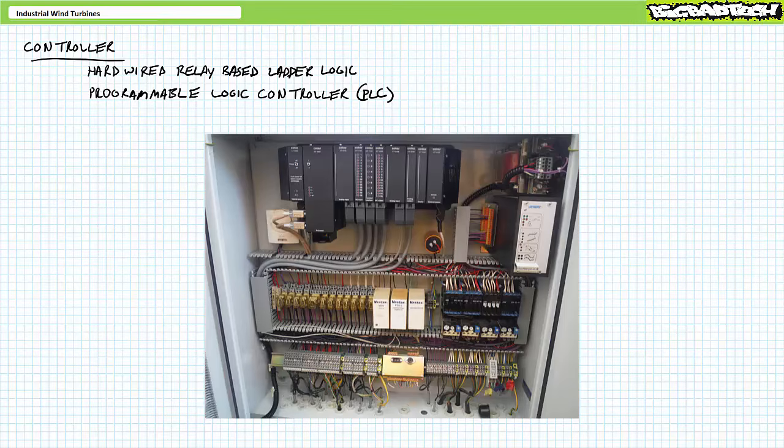Depending upon construction, the controller takes inputs from various sensors and switches, evaluates these inputs, and issues outputs to actuators like motors and brakes. The evaluation of inputs might be real electromechanical contacts wired together, or they may be programmed instructions inside a PLC. Depending upon the model and date of manufacture, interacting with the controller can at times be an all-consuming affair of digging through sheets of schematics and tracing individual wires, plugging in some accessory interface device with limited functionality, networking a laptop with a PLC, or, if sufficiently modern, using a human-machine interface or HMI screen to do so.